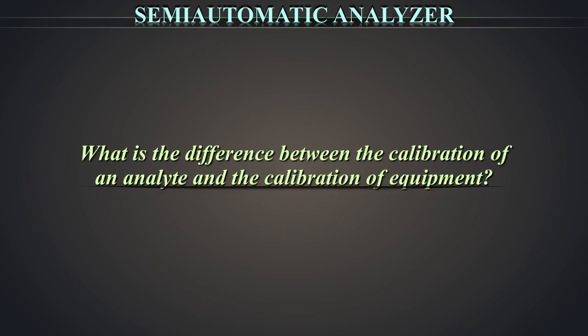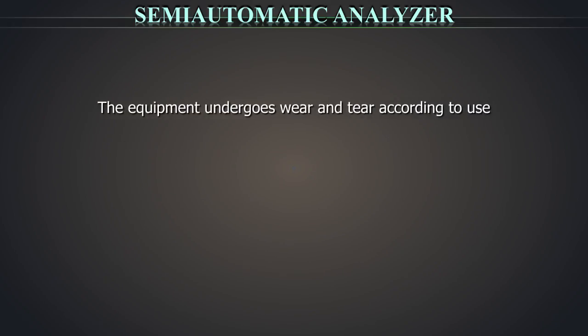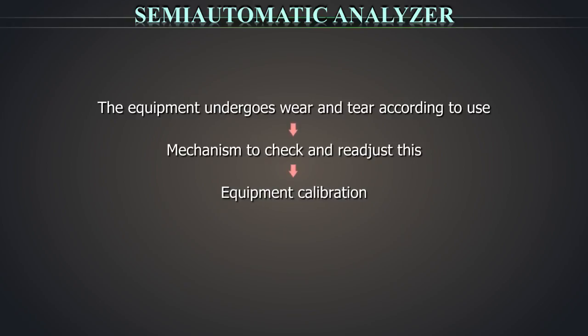What is the difference between the calibration of an analyte and the calibration of equipment? What we were talking about so far was about calibrating an analyte. The equipment also undergoes wear and tear according to the use. So there has to be a mechanism to check and readjust this. This is called an equipment calibration.